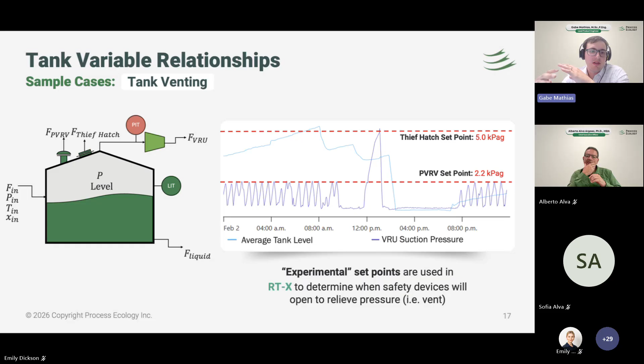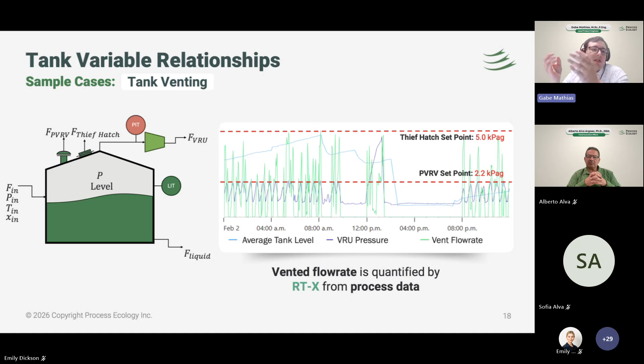There's even a case in this data at 12 p.m. where the PVRV wasn't enough to relieve the pressure, and it kept climbing. And then you had your thief hatch open, and so you have the thief hatch set point at that point. So it's a very physical phenomena. The safety devices have a weight in them, and if it reaches a certain pressure, then that weight gets lifted. It's very physical, very deterministic. Next slide is what RTX calculates. So every time the safety device opens, we calculate a flow rate from the safety device based on physics, based on modeling the tank itself.